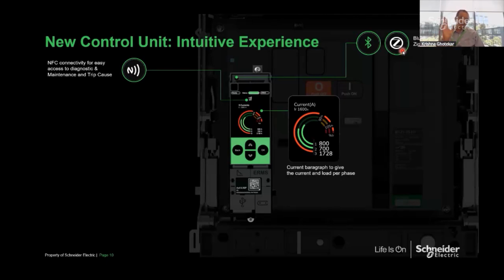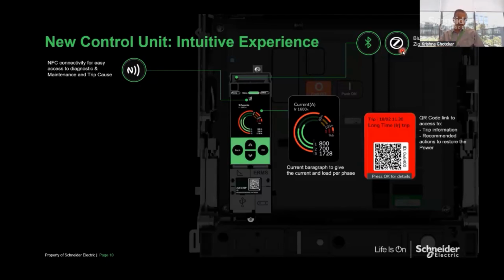So that means for a facility or for an electrician in the electrical room, even from a distance he can know if my phase, if my load is going into the overload zone, with a color indication. And of course it comes in numerical format also. Once the breaker trips on fault, the display will turn red in color, and a QR code will be displayed on it, so that if you scan the QR code, you will get all the fault diagnostics and also the recommended actions to restore the breaker, depending on the type of fault the breaker has tripped on.